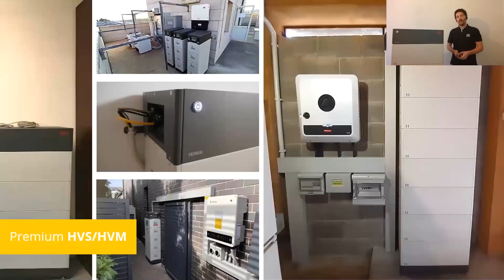Here you see some examples of how an installation could look. And after the installation, if the system should be extended, it's important in this high voltage system to have a similar state of charge in all modules. As modules arrive with about 25 to 30% state of charge, the original battery should be turned off at about the same SOC. Then the new modules can simply be added. And after this, the configuration has to be done again with a new module quantity. A small tip: the customer who wants the extension could simply turn off the battery at about 25 to 30% SOC. Then the installer can simply go on site, add the module, do the configuration, and then the extension is done in just a few minutes.